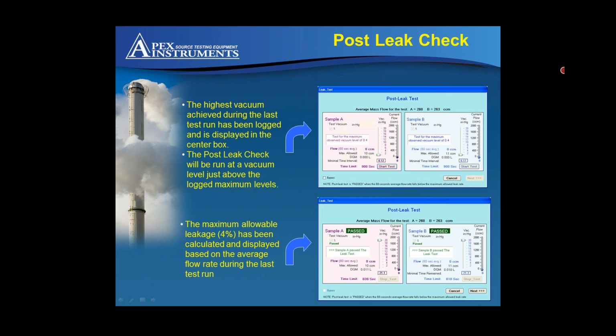Once you've completed your test, you go into your post-leak check, which looks identical to the pre-leak. The only difference is you actually run it at a little bit lower vacuum.